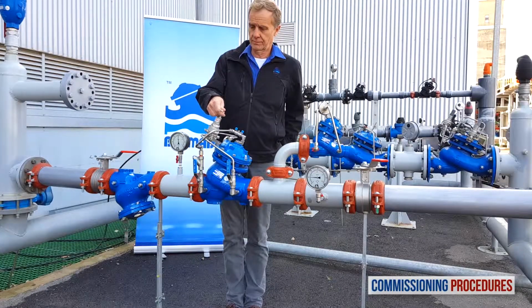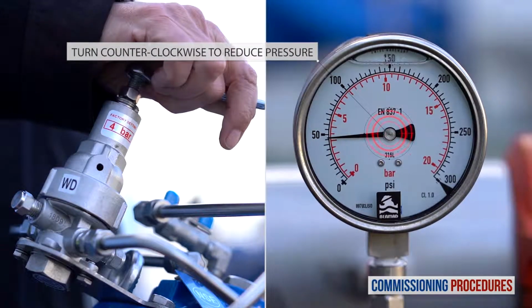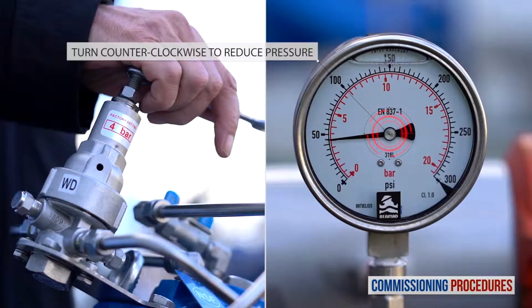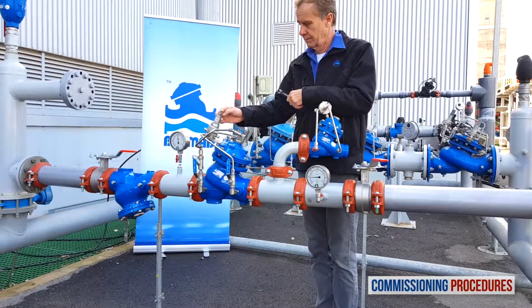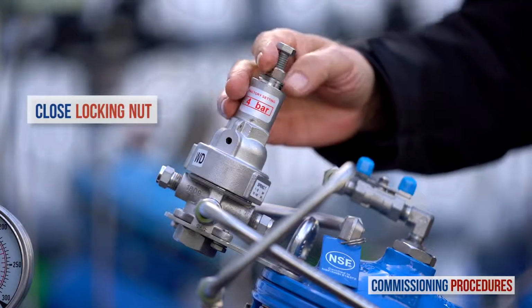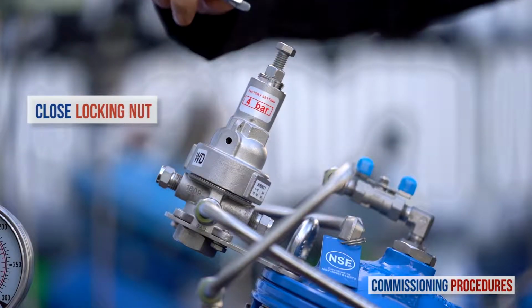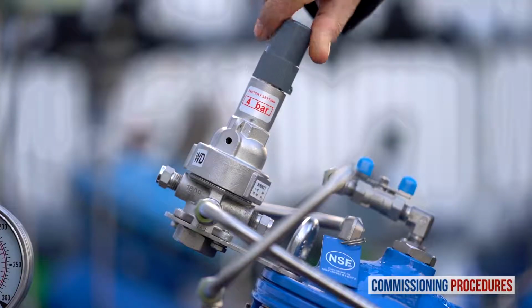To reduce the downstream pressure, follow the same process, but in this case turn the adjustment screw counterclockwise. Once you have reached the desired downstream pressure, close the pilot adjustment screw locking nut and replace the protective cover.